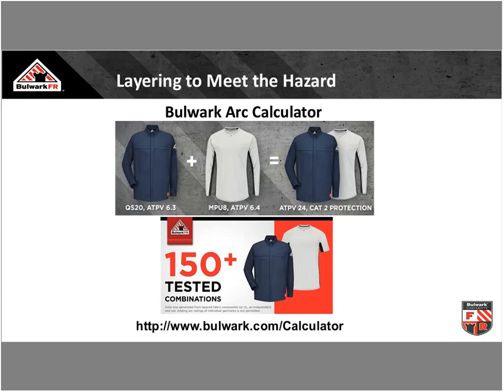Your system's not 24. What is your system? Your system is going to depend on what your pants are. Your system is going to depend on what the lowest ATPV in that system is. That's what your system is going to be. If you have a 12 cal pant in that scenario, you have a 12 cal system, not a 24 cal system.